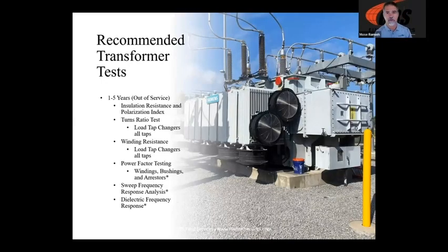So let's talk about transformers really quick. What do we recommend? Generally speaking, transformers should be maintained every 1 to 5 years. We're going to do things like insulation resistance, and a turns ratio test to check the ratio of the transformer. Winding resistance test: this is a great test to check internal connections and components, including our load tap changers. Power factor testing, I'll talk a little bit more about that. Sweep frequency response: this is not a test that needs to be done all the time, but it can have some super valuable information, and I'll show you that. And then, kind of that new test category, here is one about dielectric frequency response.